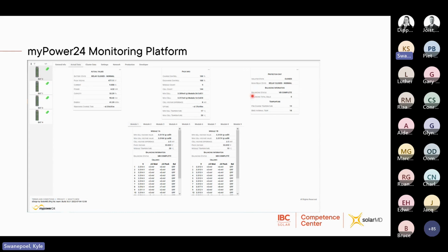Balancing information: you can come here to see if the battery is busy passively balancing. VB complete means that the voltage balancing is complete. Currently, we are below the point where the balancing will happen, and also the current is a bit too high to start the balancing here. And there's just some more temperature information here, the BMU's internal temp, and then the pre-charge circuit.